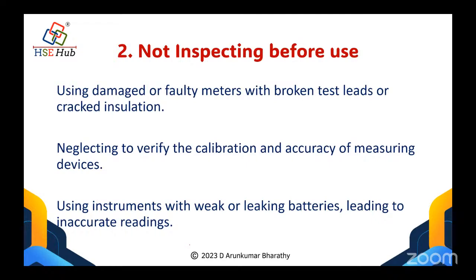I bought an equipment, every day I do 20, 30 measurements, then the calibration schedule, yearly I have to calibrate, that may be 3 months or 4 months. But generally the standard says every 180 days we have to calibrate the instrument. But many industries are following yearly ones also. But it is recommended to calibrate every 6 months, but again purely based on your frequency of usage, right?